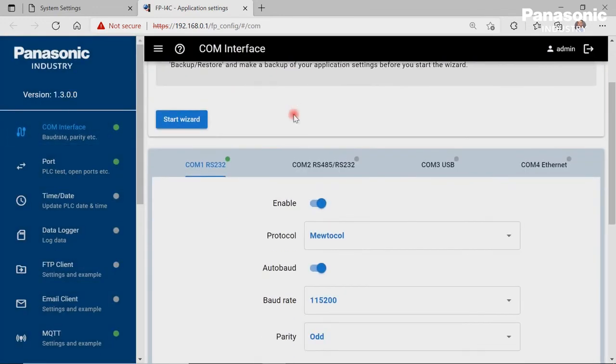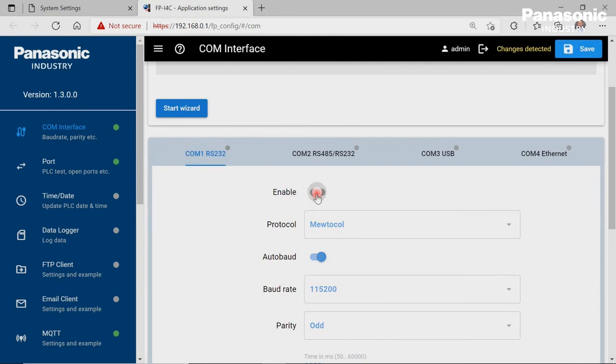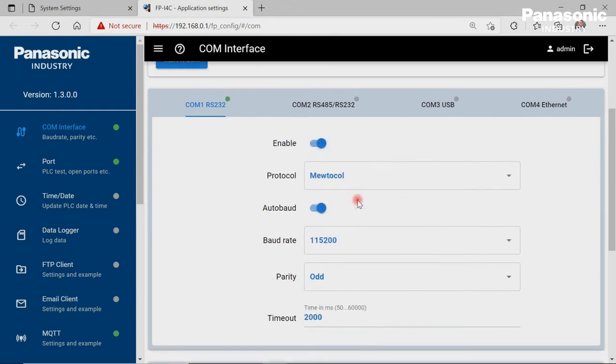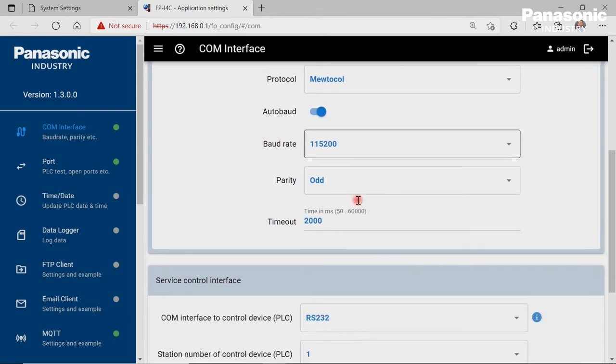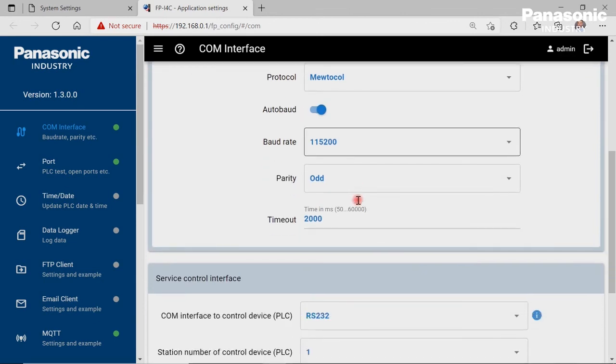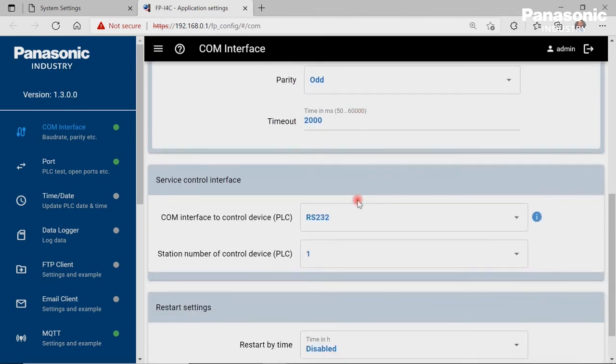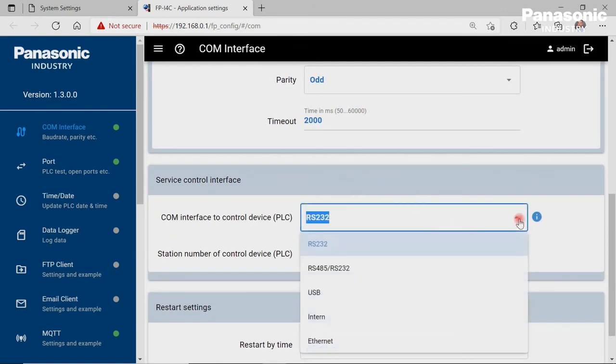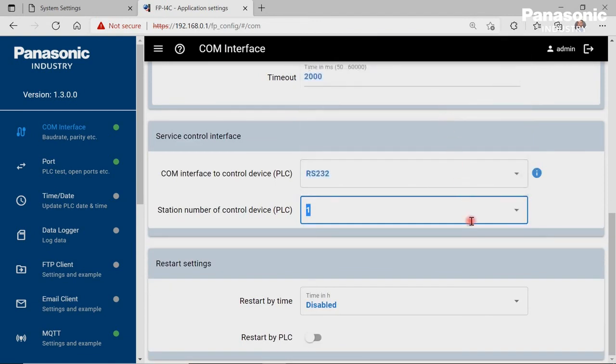We make sure that COM1 port of the FP-I4C unit is enabled. We make also sure that the configuration settings for COM1 port are equal to the settings in the PLC for COM0 port. We select from the COM interface to control device drop-down menu RS232 and set the station number to 1. This station number must be equal to the station number which we set in the PLC before.